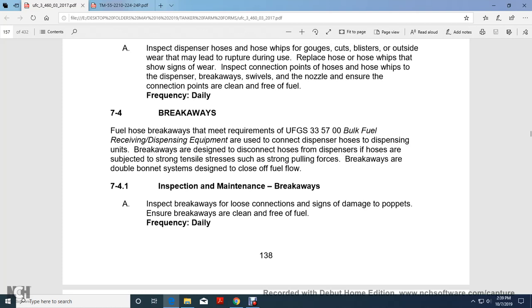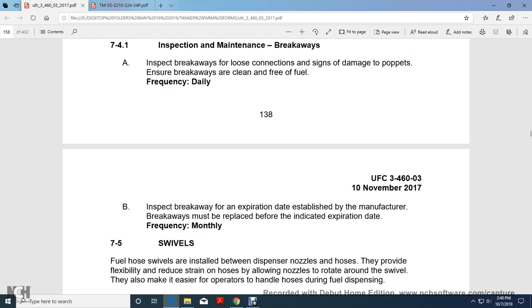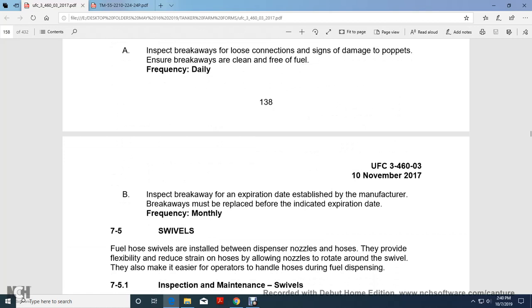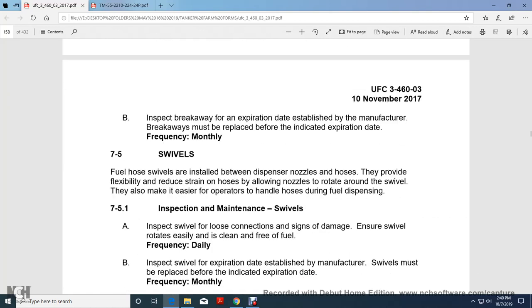7.4.1 Inspection and maintenance, breakaway. Inspect the breakaway for loose connections, signs of damage, and poppets, and ensure the breakaways are clean and free of fuel daily. Inspect the breakaway against the expiration date established by the manufacturer. Breakaways must be replaced before the expiration date, monthly.